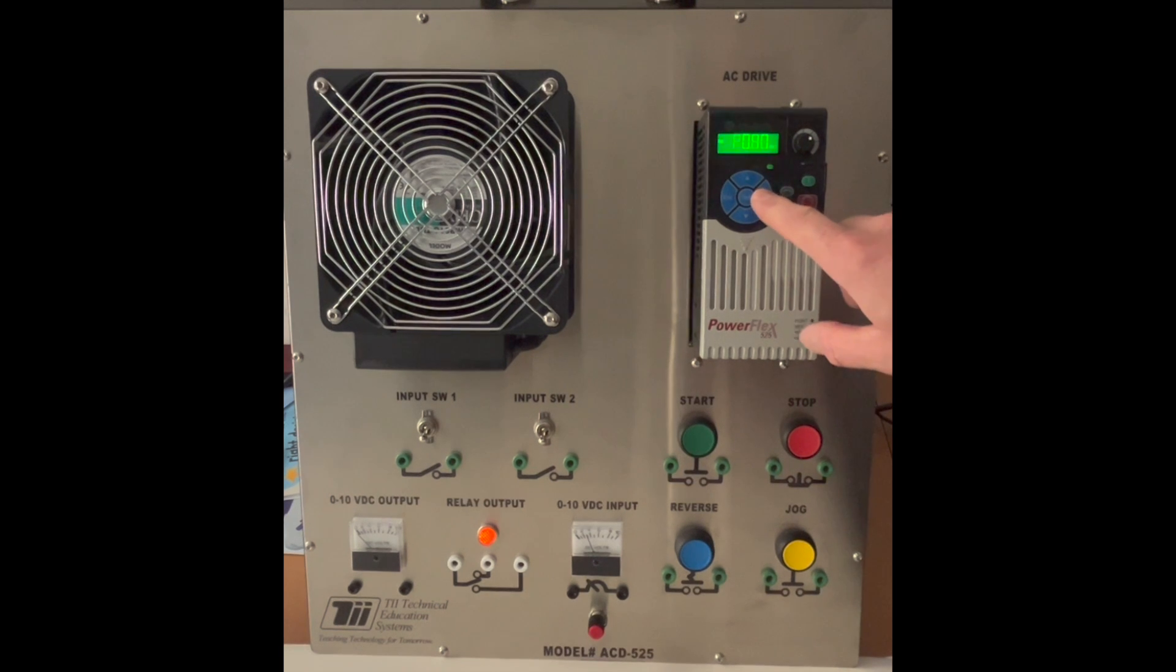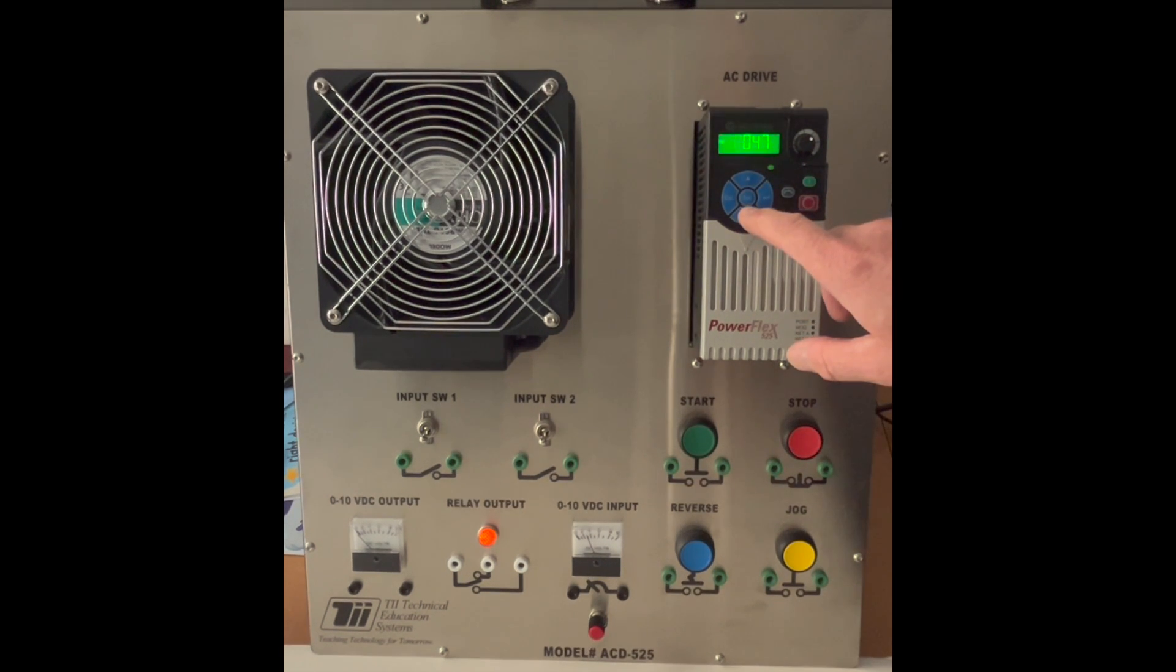So what we're going to do is we're going to enter into the menu. To set the speed reference we want to go into P43. We will hit enter. This is set to 1, which means that you're going to use the drive potentiometer right here.